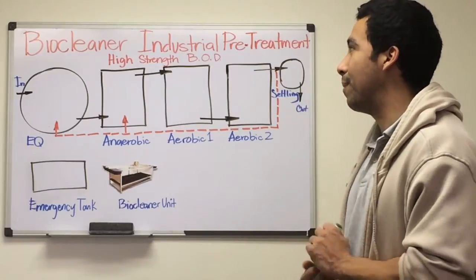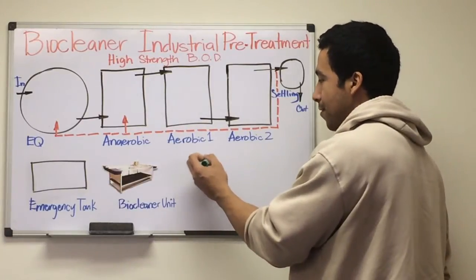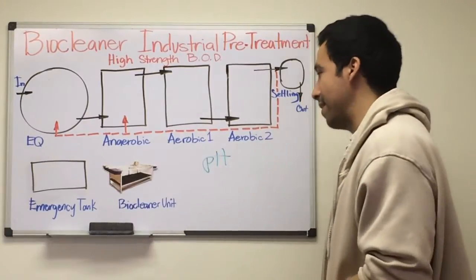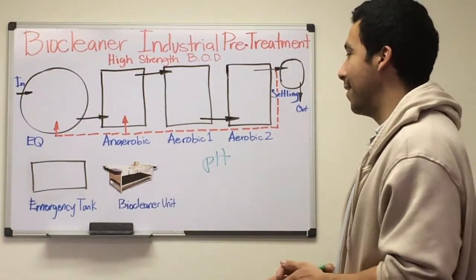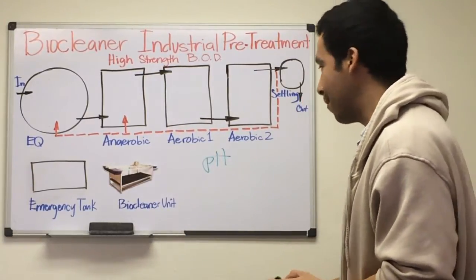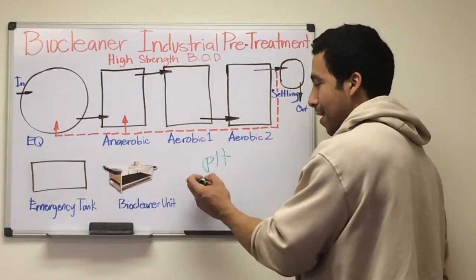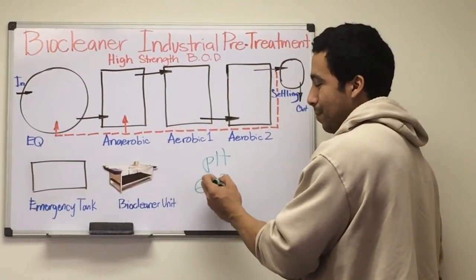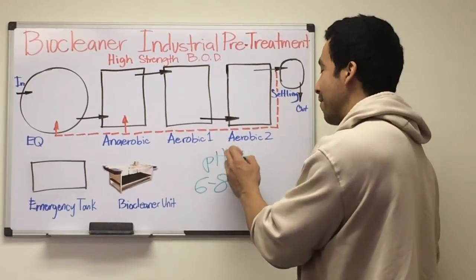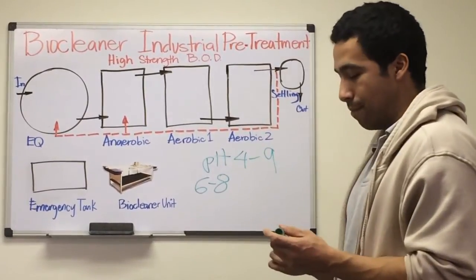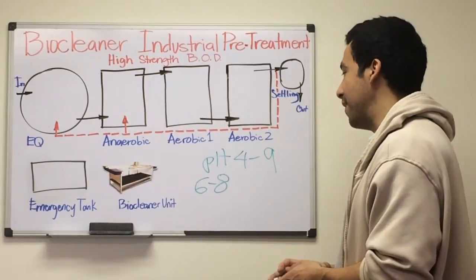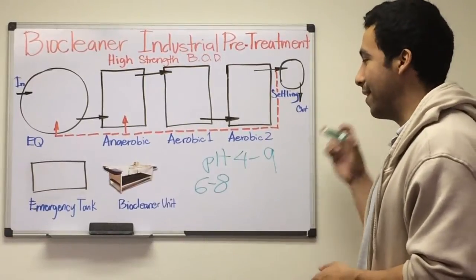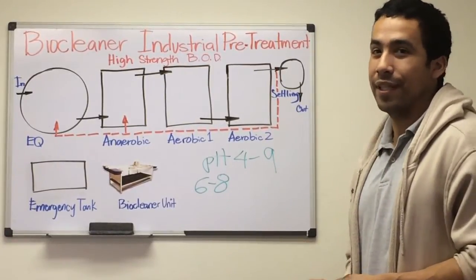One variable is pH. Usually pH will vary depending on the industrial process. For our system, our microorganisms operate at an optimal pH of 6 to 8. However, we can survive from 4 to 9. If it's below 4 or above 9, you might consider having a neutralization tank where you can either increase or decrease the pH.